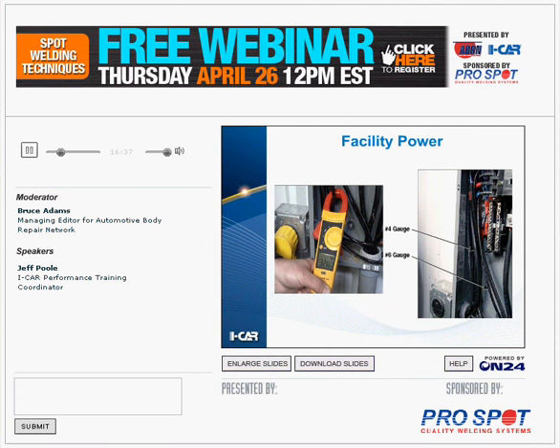So this is where it's going to be really important to make sure that we're testing the available voltage and current at each outlet, and typically while the equipment is actually under load, because this is really going to spell out where we're at.